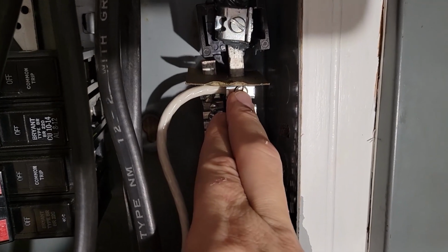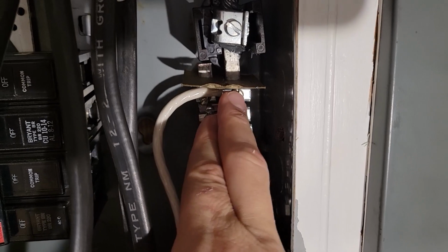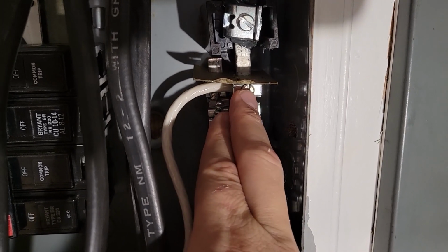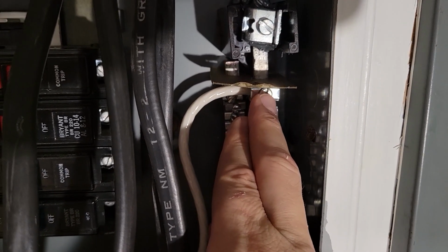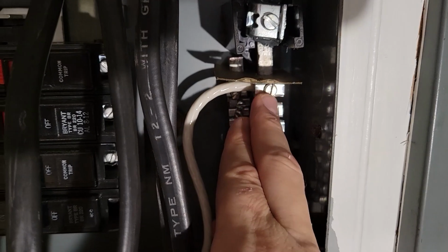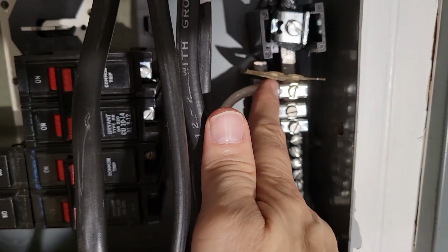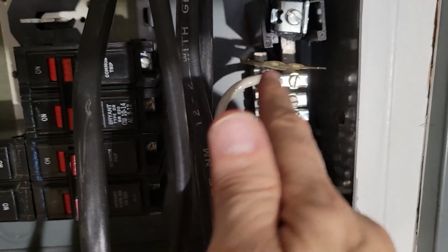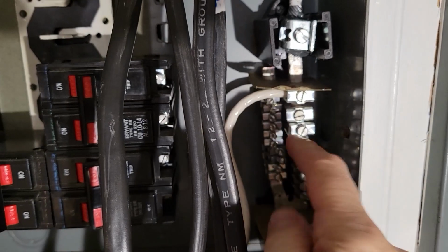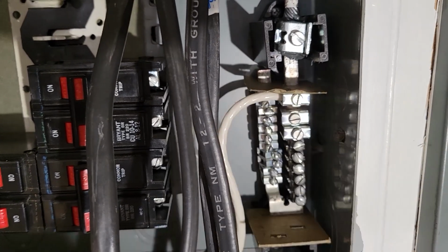One other tip is you tighten it, loosen it, tighten it, loosen it, tighten it. So like 3 cycles, and that really helps compact the wires, because once you cut the insulation off, they tend to want to spread out. So you just want to make sure they're nicely bundled so they're making a really good connection.